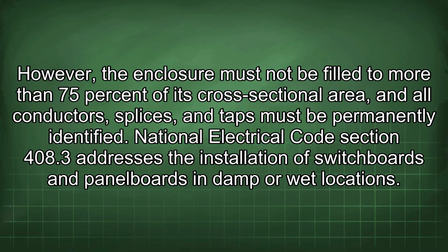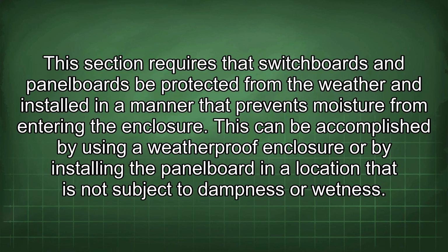National Electrical Code Section 408.3 addresses the installation of switchboards and panel boards in damp or wet locations. This section requires that switchboards and panel boards be protected from the weather and installed in a manner that prevents moisture from entering the enclosure. This can be accomplished by using a weatherproof enclosure or by installing the panel board in a location that is not subject to dampness or wetness.